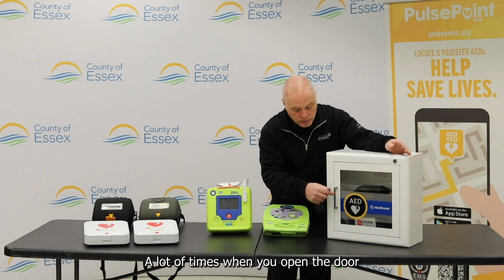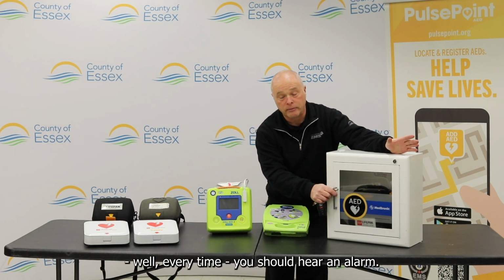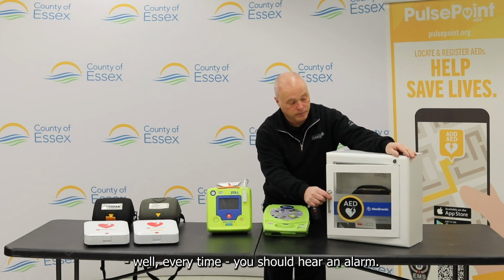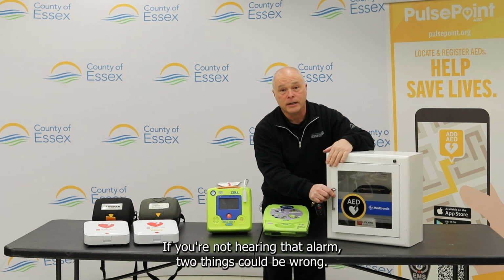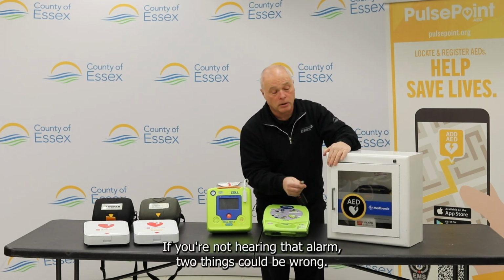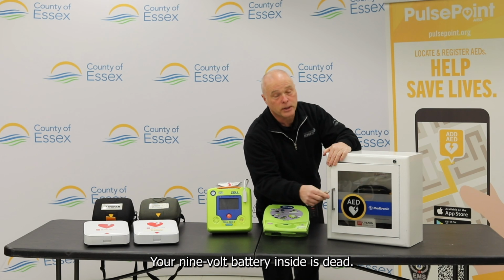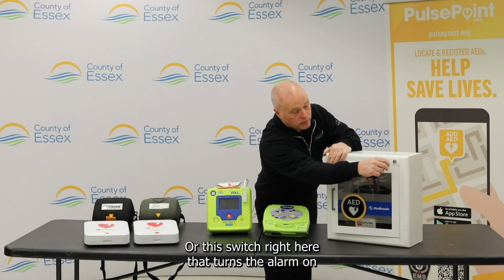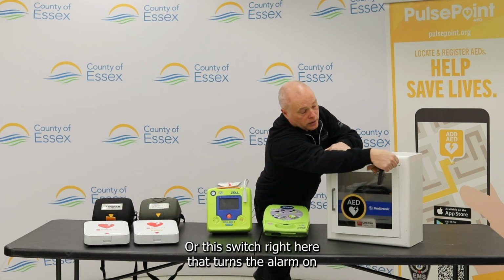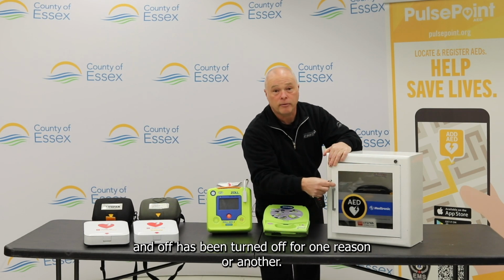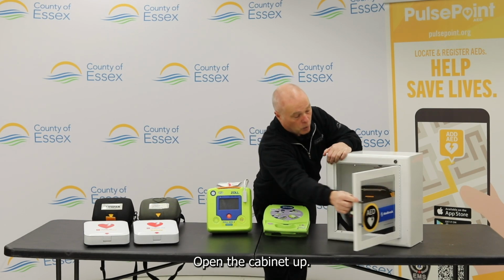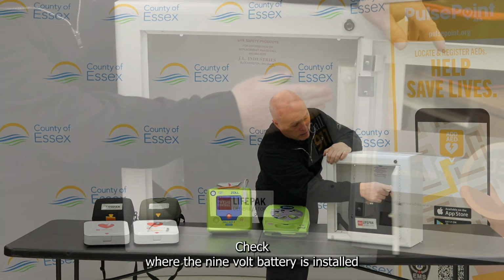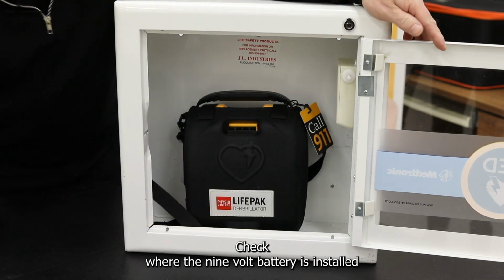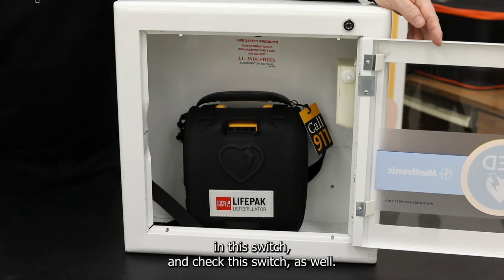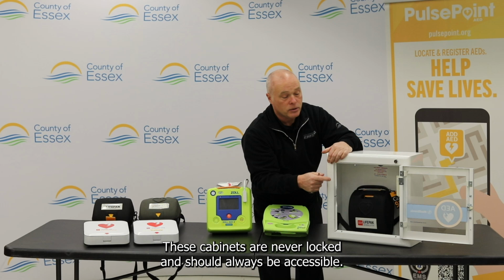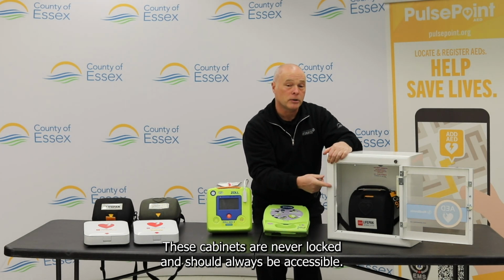A lot of times when you open the door, well, every time, you should hear an alarm. If you're not hearing that alarm, two things could be wrong. Your 9-volt battery inside is dead, or this switch right here that turns the alarm on and off has been turned off for one reason or another. Open the cabinet up, check where the 9-volt battery is installed in this switch, and check this switch as well. These cabinets are never locked and should always be accessible.